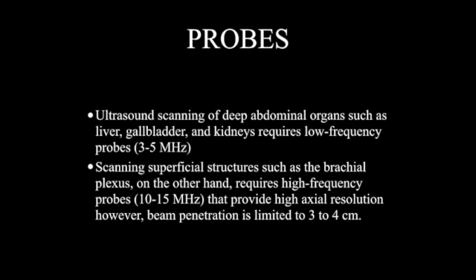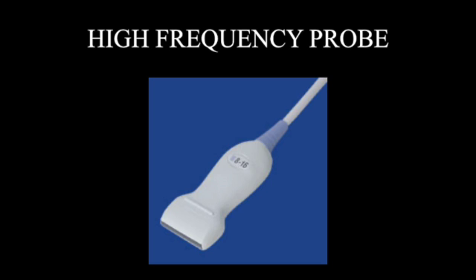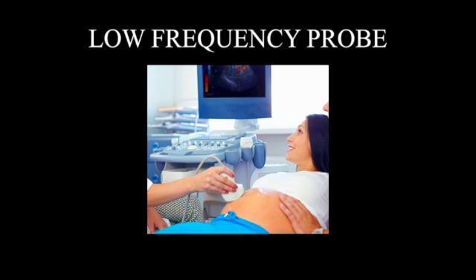A high-frequency probe can provide adequate resolution; however, the beam may only penetrate 3 to 4 centimeters in depth. Here's an example of a high-frequency probe, and here's a low-frequency probe.